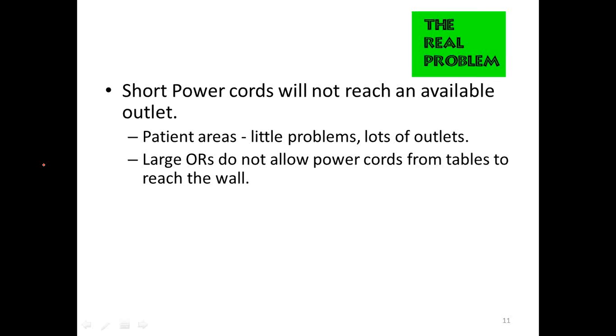In operating rooms, we don't like to put outlets in the floor because they hose down the rooms to clean them and they can get wet. We can't put them on suspended ceiling connectors for the most part because it gets in the way of the sterile field.